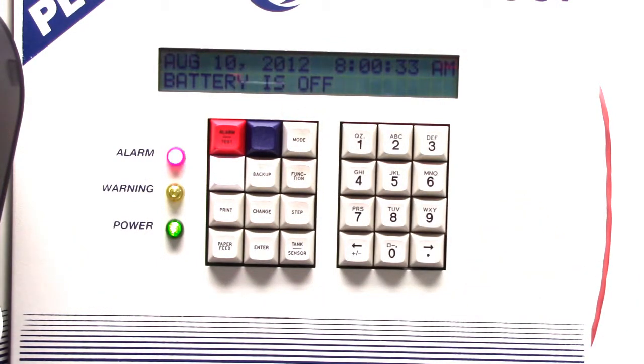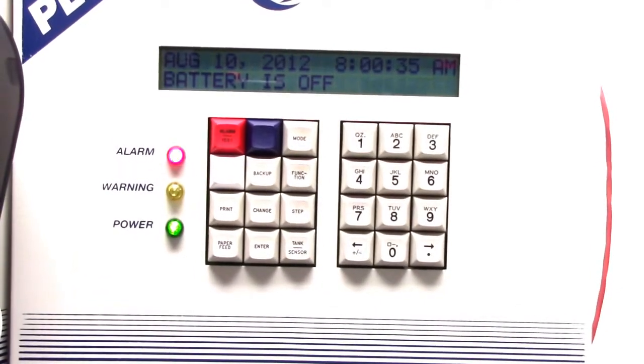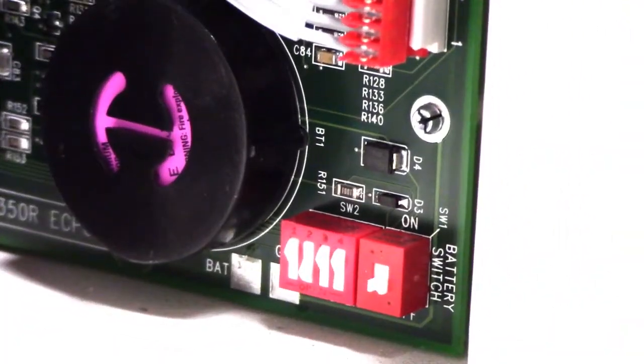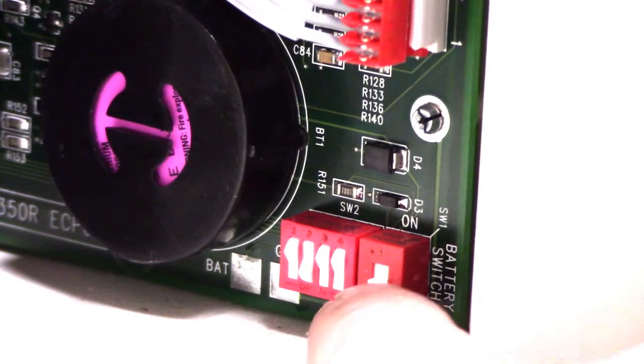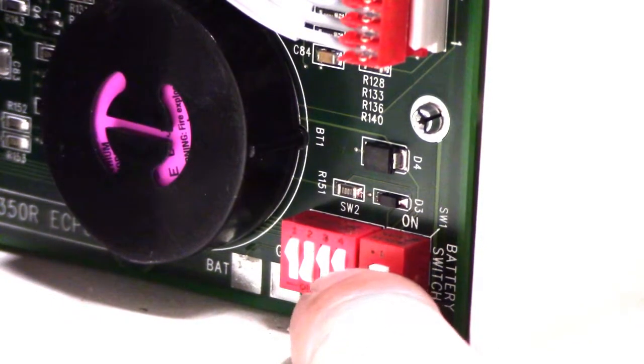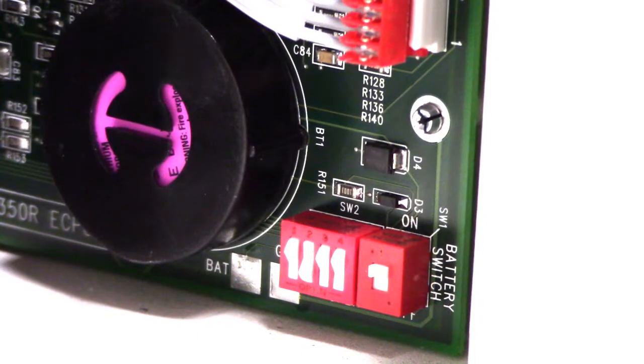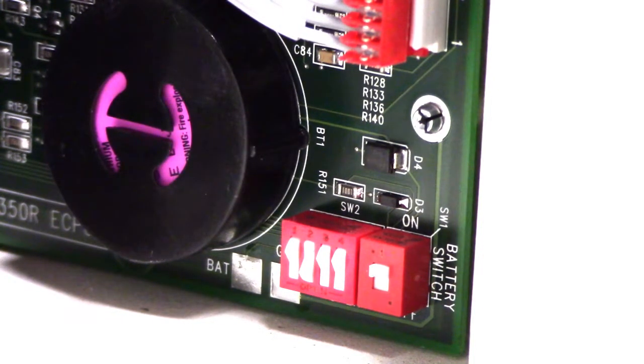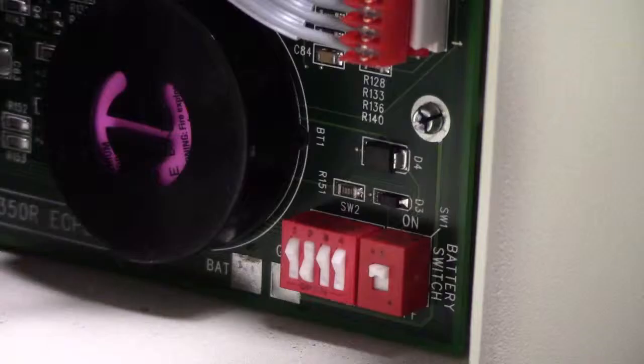From here, back behind the printer door, so while that is restoring, we're going to go ahead and turn our battery back on, then walk away. It's going to take anywhere between 5 and 20 minutes for this tank monitor to reprogram itself from the stored backup that it holds internally. You'll know that it's done because the tank monitor is going to print out the entire setup for you that it has just restored.